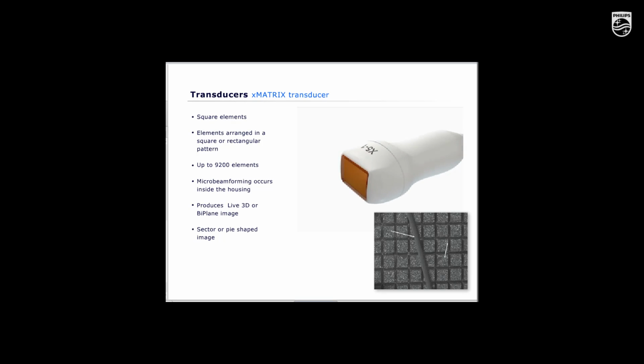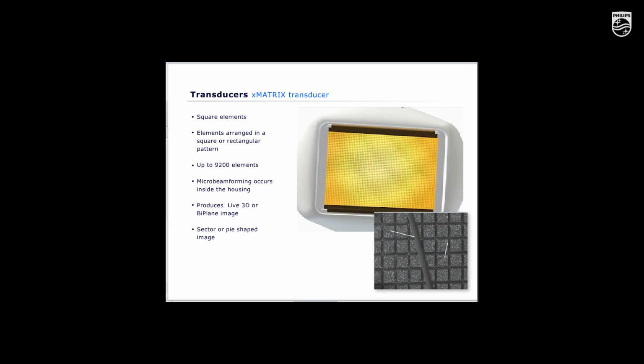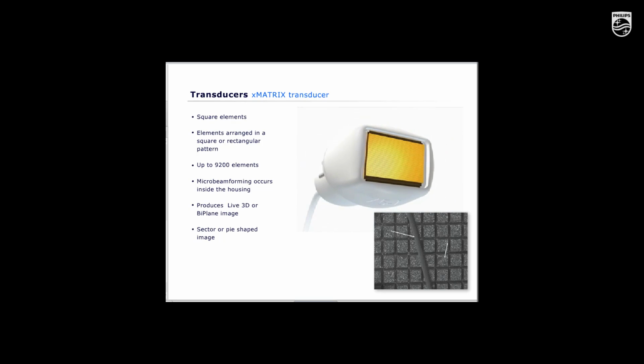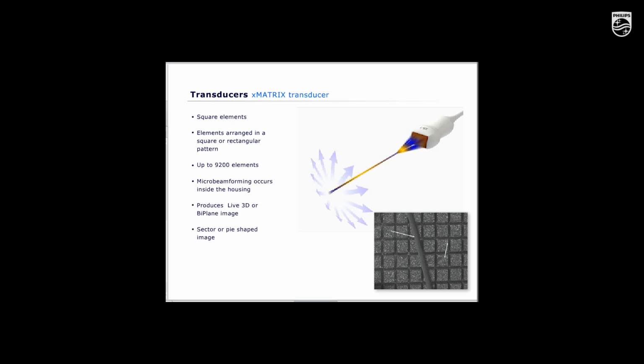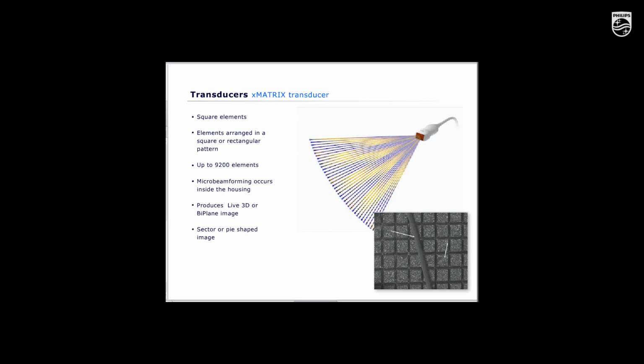Unlike other imaging transducers, X-matrix transducers have square elements instead of rectangular. This image is a magnified X-matrix array showing individual elements and a human hair for scale reference. Depending on the application and design, it may contain up to 9,200 elements. Matrix transducers have technically the same principles as sector transducers, but a matrix transducer consists of many more elements and has elements in two directions in a matrix pattern, while other transducers use an array.